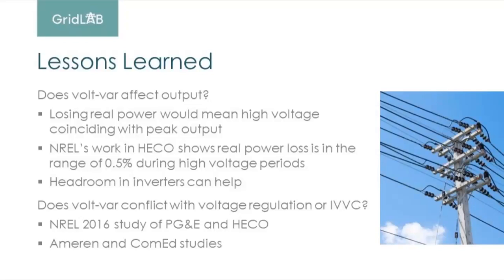But number one, we're pretty convinced that the potential losses from volt-VAR are very small, and that there are relatively straightforward ways to mitigate those losses. One is by having headroom, so you can have an inverter that has a little bit of extra kVAR capacity, so it can be rated at, let's say, 0.9 power factor for full output. That's pretty typical in the utility scale world, where you'll have inverters that are rated at 0.9 power factor. So that's something that we may want to start thinking about doing on the distribution side as well.